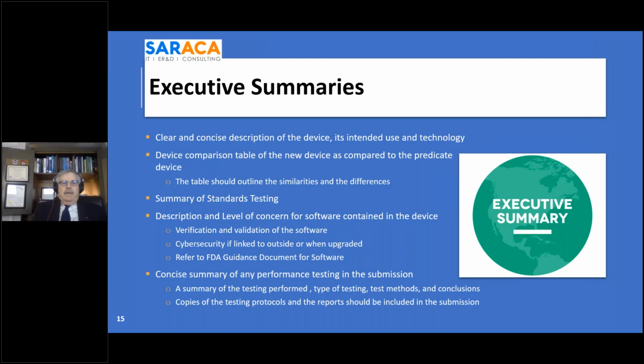The device comparison table of the new device as compared to the predicate device. You need a table that outlines the similarities and the differences. And this should include things like weight, intended use, if it's a laser, how the laser is generated, the number of volts that is required, the pulse length, the pulse standard, things like that. Same thing as you would do for a balloon catheter, burst strength, material that it's made out of, and so forth. You need to have a summary of the standards testing.